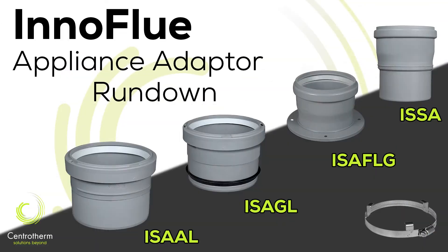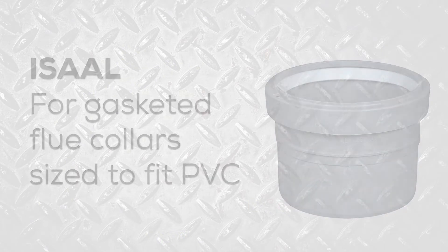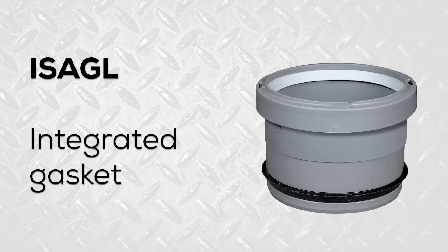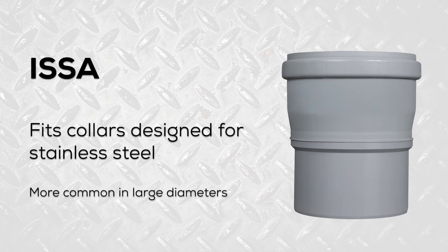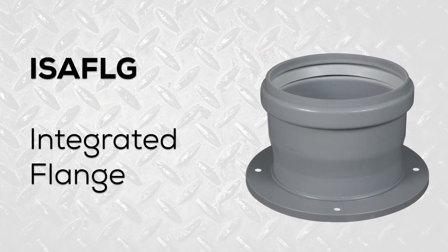Now let's run down the most commonly installed InnoFlue adapters. ISAAL adapters fit gasketed flue collars sized for PVC. Our ISAGL adapters have an integrated gasket. Our ISSA adapters fit collars sized for stainless steel, and sometimes our ISAFLG is the right component due to the flange.